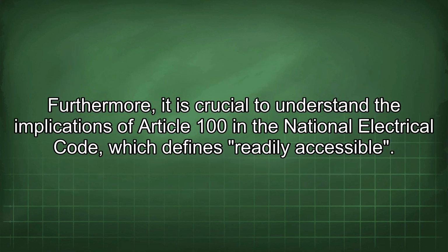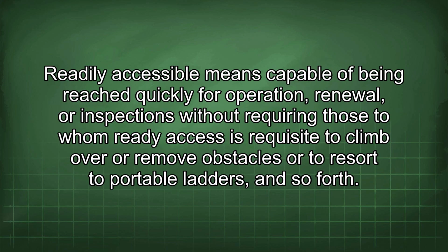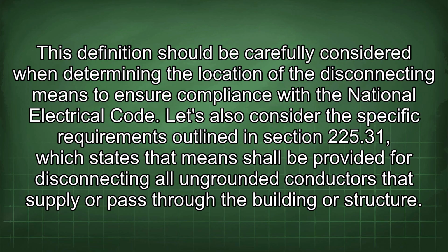Furthermore, it is crucial to understand the implications of Article 100 in the National Electrical Code, which defines readily accessible. Readily accessible means capable of being reached quickly for operation, renewal, or inspections without requiring those to whom ready access is requisite to climb over or remove obstacles or to resort to portable ladders, and so forth. This definition should be carefully considered when determining the location of the disconnecting means to ensure compliance with the National Electrical Code.